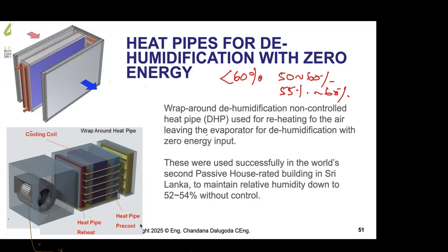You know what we do? We use a heat pipe system. That means, this is return air hitting the cooling coil and becoming supply air. Return air 24 degrees C, supply air 12 degrees C. Now, instead of hitting the cooling coil directly, return air first hits another coil where the 24 degrees C heat comes and drops in front of the cooling coil for reheat. See, this kind of a thing.